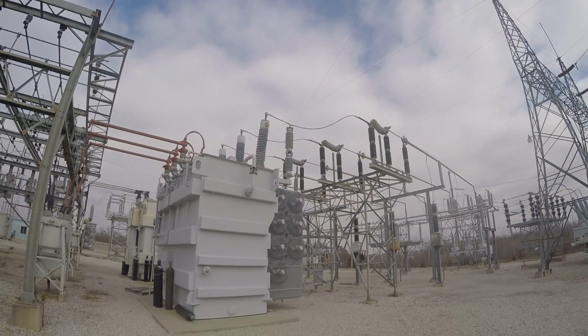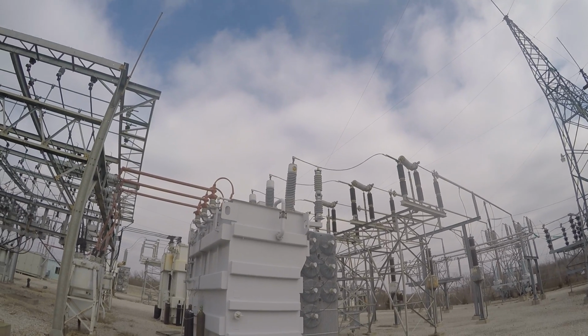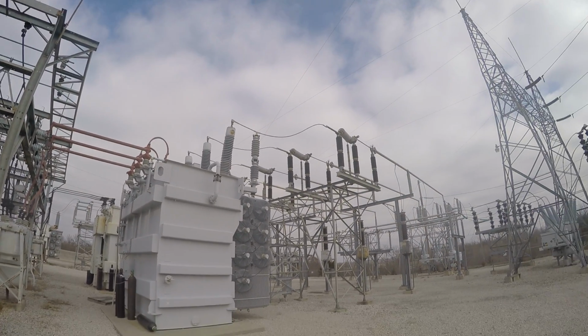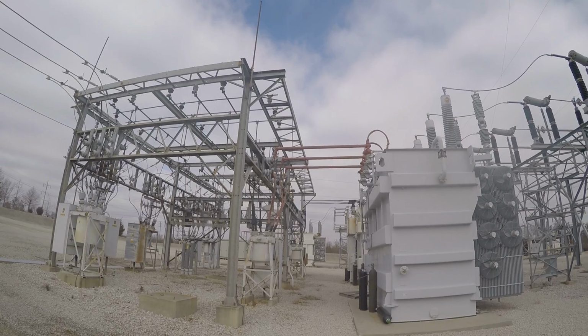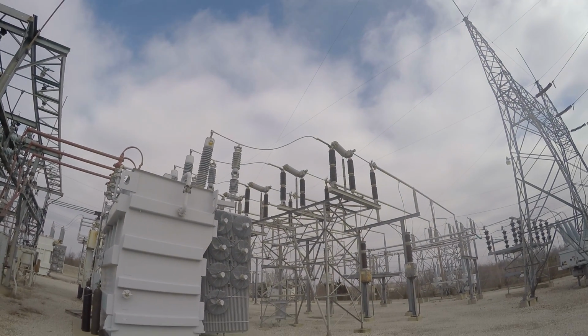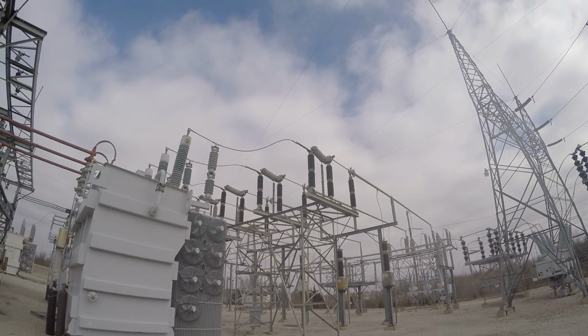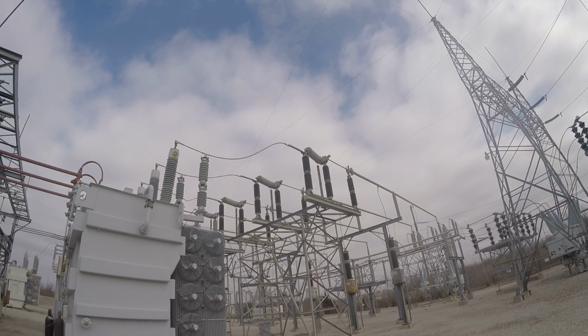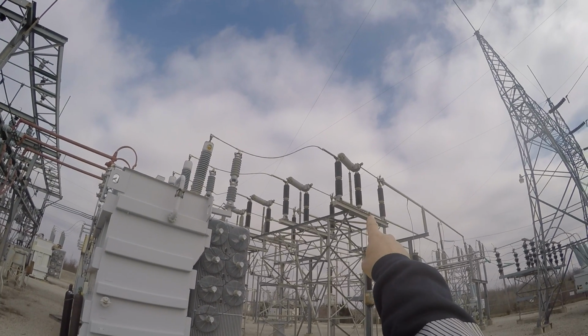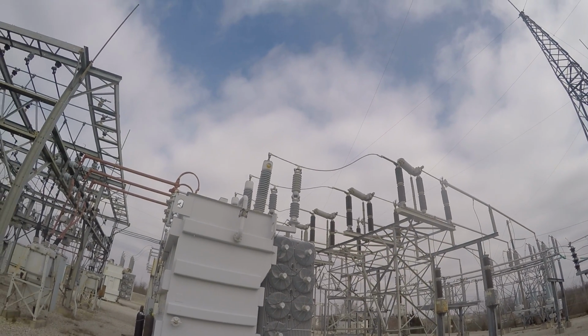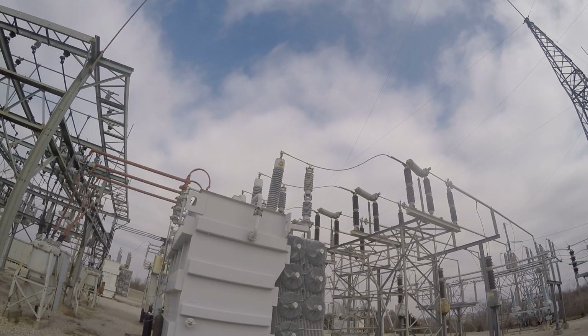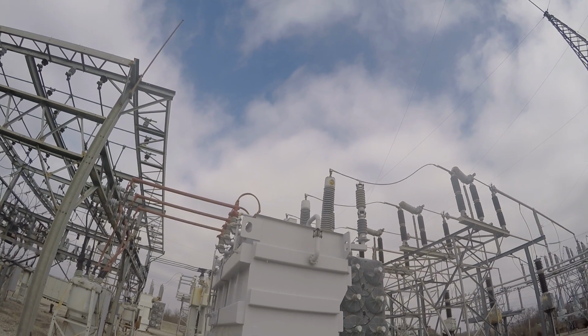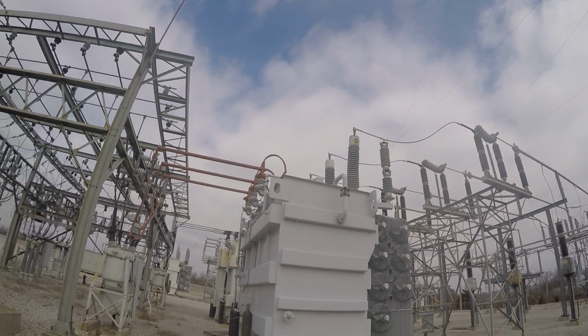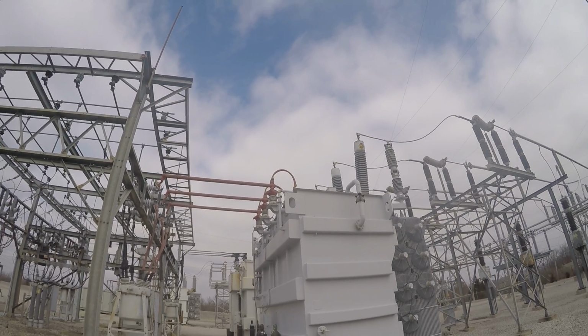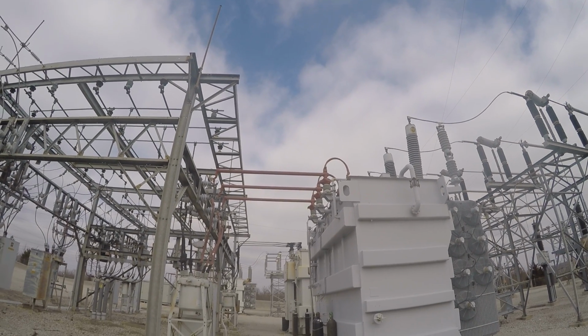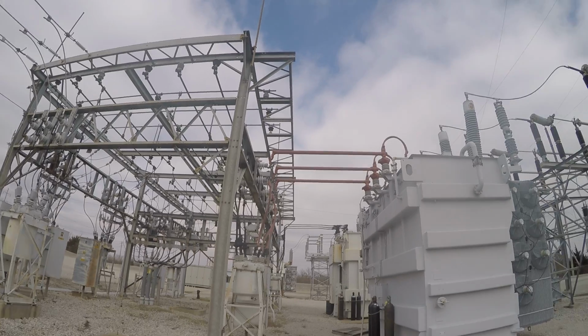Okay, I was at the east substation. I'll just walk through from the transmission line down to the breakers here at the sub. It's a 161,000 volt transmission line coming in on that bus bar, and then these switches that can be opened to isolate this transformer. On the right hand side, you come in 161,000 volts into that transformer, and it comes out the low side 7200, which we use on our circuit lines.